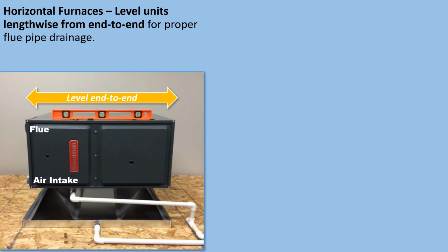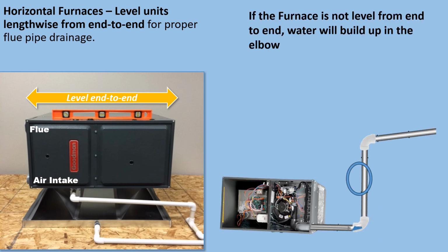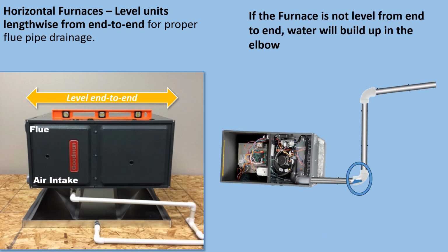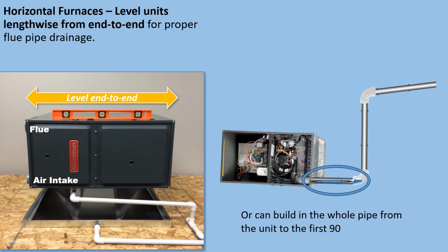Horizontal furnaces: level units lengthwise from end to end for proper flue pipe drainage. If the furnace is not level from end to end, water will build up in the elbow, or it can build up in the whole pipe from the unit to the first 90. And if this happens, obviously the unit is not going to operate.